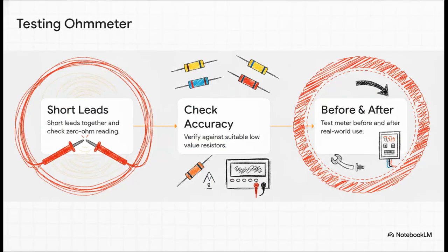But hey, just owning the right tool isn't enough, right? You have to prove it's telling you the truth. On the ohm scale, you first need to short the leads together and check for a true 0-ohm reading. After that, you verify the meter's accuracy against known low-value resistors, specifically 0.1, 0.5, 5, and 10 ohms. And the golden rule here, you do this before and after you test the installation. Because think about it, if your meter drifts or breaks during the job, all your results are totally compromised. You are proving your tools are perfectly calibrated before you trust them with someone's life.